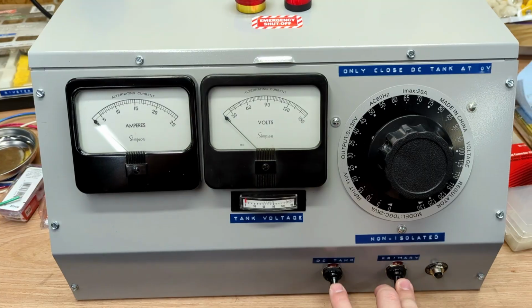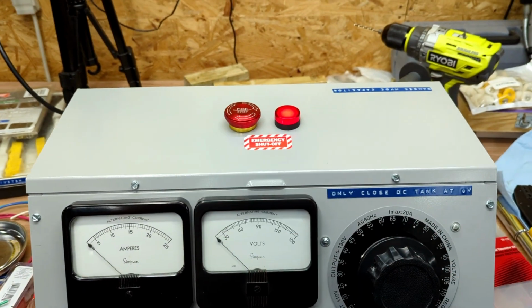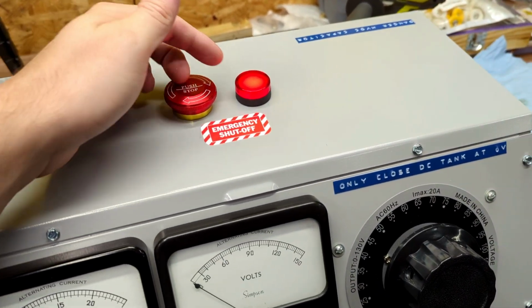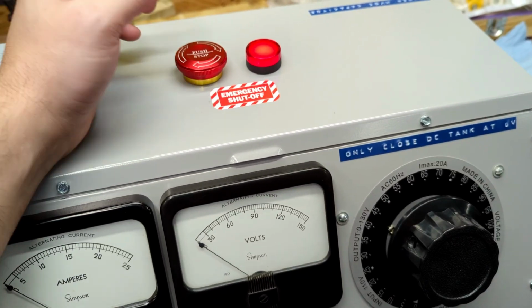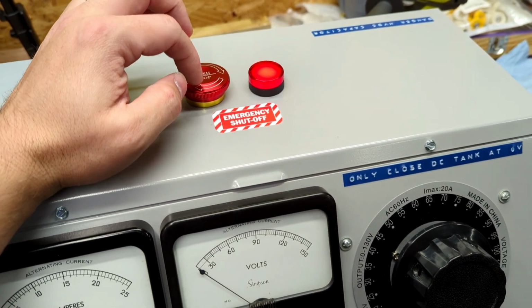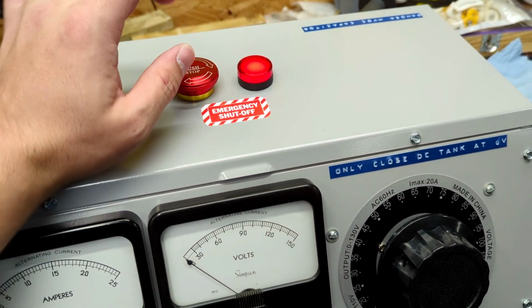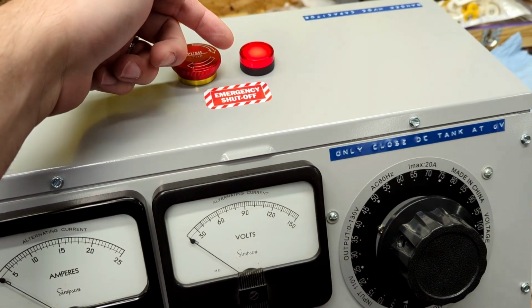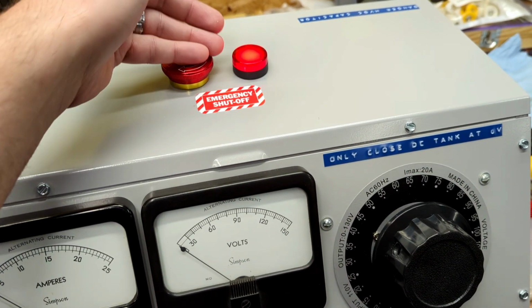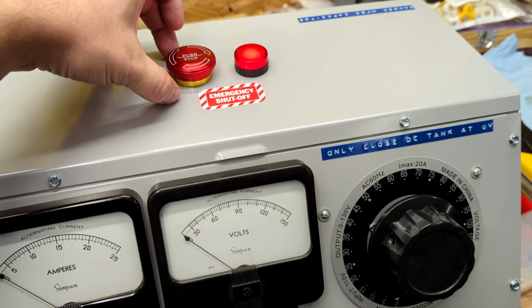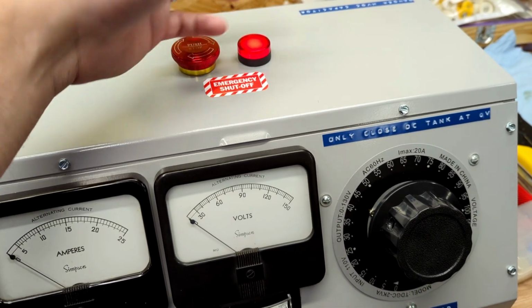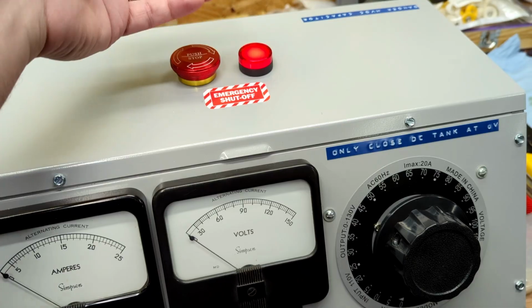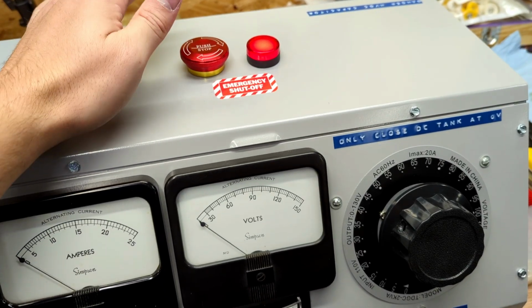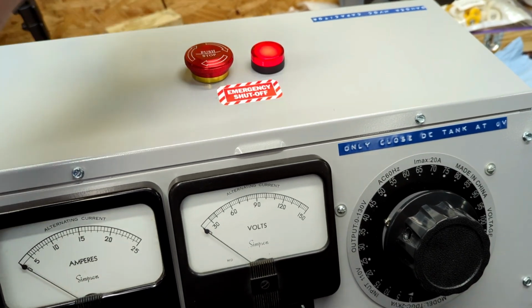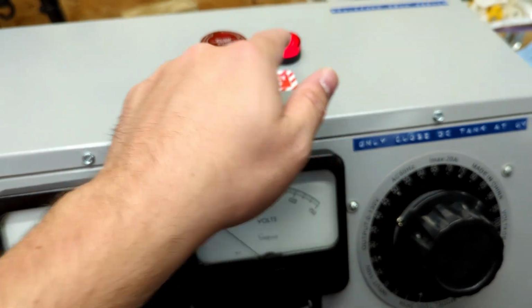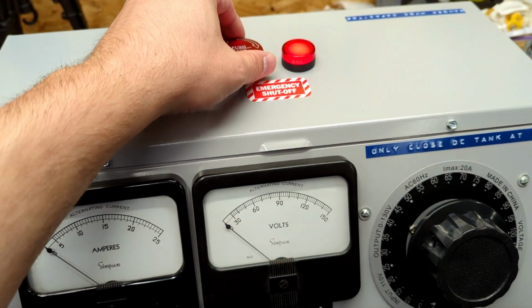So e-stop works. This light looks pretty dim on camera, but it's very bright in person. The e-stop switch directly powers the LED, so even if all this circuitry is disconnected, that light will come on no matter what, because it's directly between a normally open contact on this and neutral. So as long as you've got power and you e-stop it, you're going to see something here. Normally, if I'm doing work on something, I can e-stop this, and if I see the red light, I know that the entire system is disengaged.